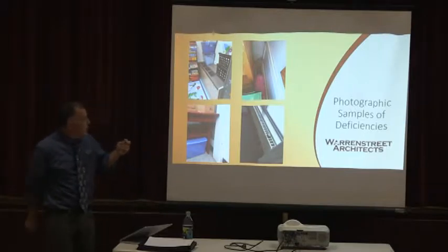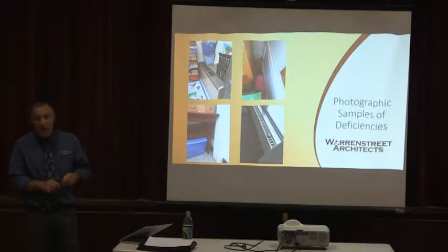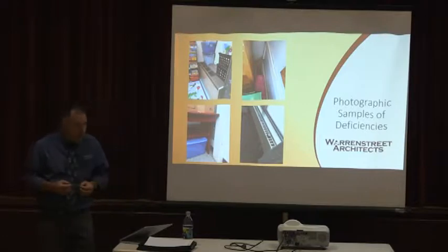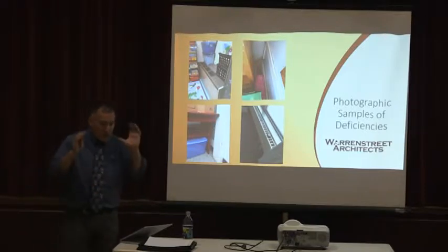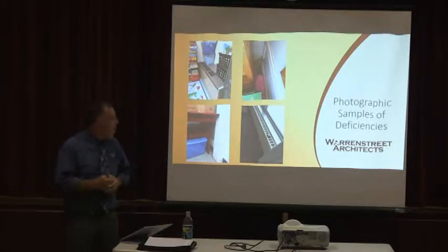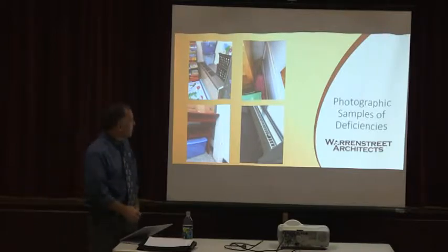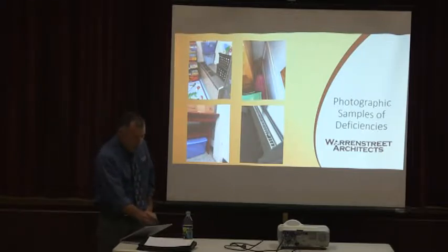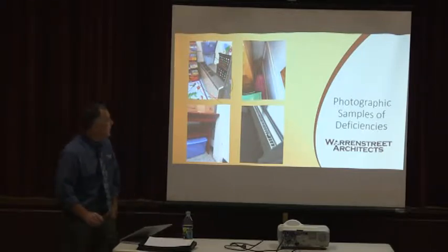Most of the building is ventilated through unit ventilators. So that means that there's a cabinet in each classroom that ventilates directly to the outside. Those are designed for a very specific purpose, and really you can't modify it. But there's a classroom, I believe this is in one of the special ed classrooms near the main office, where the cabinet was actually built over.